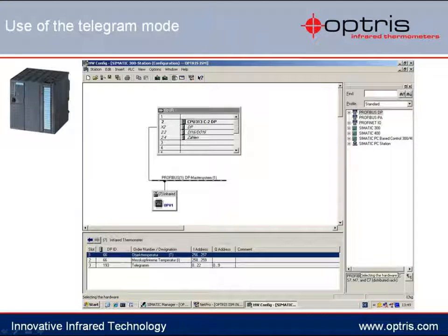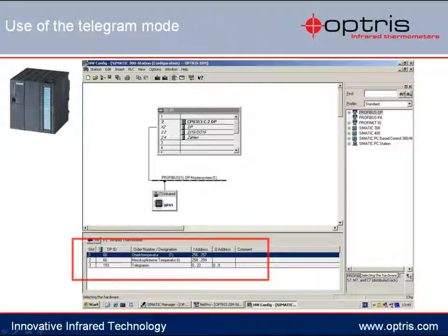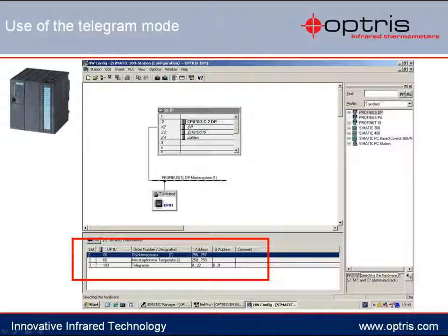After integrating the GSD file, you can already receive the object temperature and the internal sensing head temperature via the PLC. To also send and receive further orders, you will need a so-called telegram mode, which you can implement into the PLC settings as a module. With the telegram mode, you can send further orders from the PLC to the temperature sensors and receive corresponding answers from the sensors.